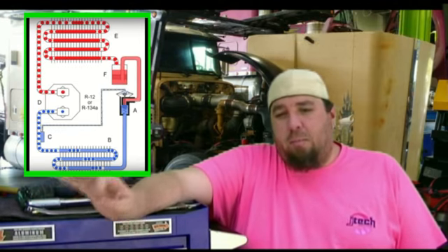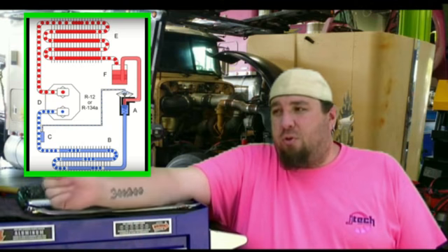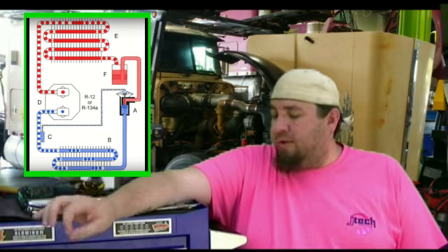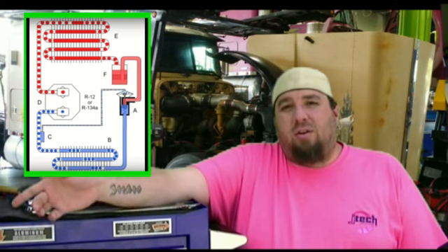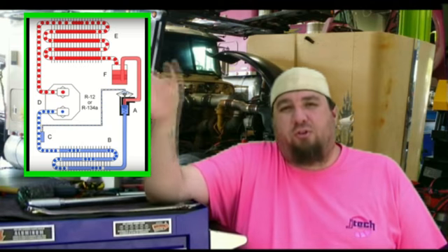Now the thermal bulb will not be in all systems. Usually it's tied in with a thermal expansion valve. The thermal bulb that I have pictured here is a standalone self-contained unit. If it goes bad, you have to replace the whole unit. It contains refrigerant, but as I said, it's self-contained. It will measure the temperature and use the coolant to transfer movement into the thermal expansion valve to make the valve open and close based on the temperature, to allow more or less of the fluid coming through.